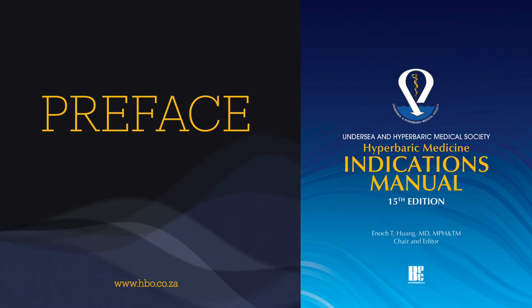And the fire risk, how does that arise? The manual explains the catastrophic fire potential. When oxygen leaks from the delivery system into the general chamber environment, it creates an oxygen-enriched atmosphere. The manual warns that when this concentration approaches 23.5% or higher, combined with the increased pressure, it can have potentially catastrophic results. The pressure itself enhances the intensity and speed of fire spread. That sounds incredibly dangerous. A volatile environment. It is. The manual also expresses concern about patients buying these types of chambers for home use without proper guidance on these potential catastrophic occurrences. That extends the safety risk into completely uncontrolled settings.